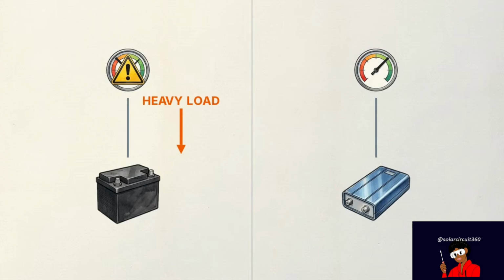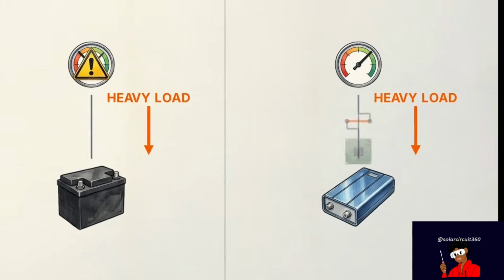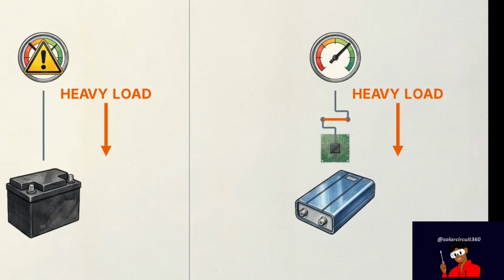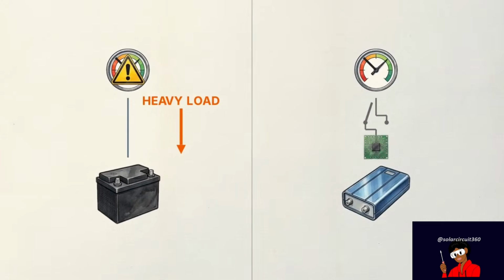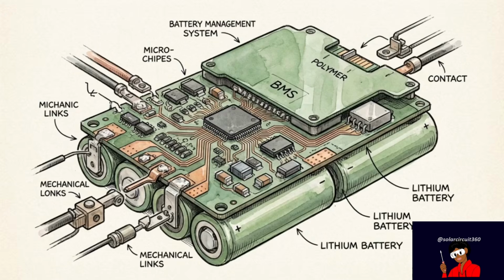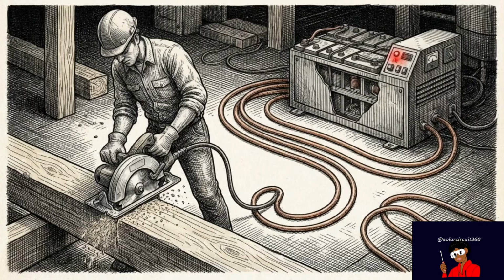The right side reveals a lithium iron phosphate battery. Lithium chemistry excels here, holding a perfectly stable voltage in the green zone even under a heavy load. However, lithium iron phosphate cells rely on a battery management system, or BMS, to enforce strict operating parameters. The BMS has a hard, non-negotiable amperage limit and will abruptly sever the connection to protect the cells from overcurrent. If you do not verify the specific discharge limits of your BMS, a premium, fully charged lithium battery will instantly cut power and collapse your entire system the exact moment a saw trigger is pulled.